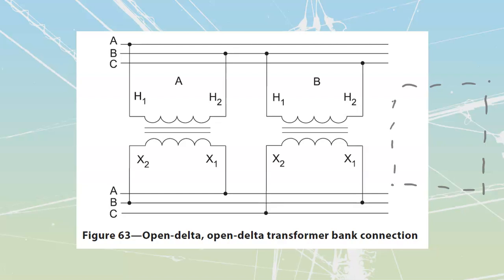The last situation is where the majority of my load is going to be single phase, and I only need a very small amount of three-phase power. For those situations, it might be where you've got a 240 volt delta line that you're feeding in. So you might be 600 on the top there, but coming over to 240 volt, with all loads line to line. We're just going to go from A to B.